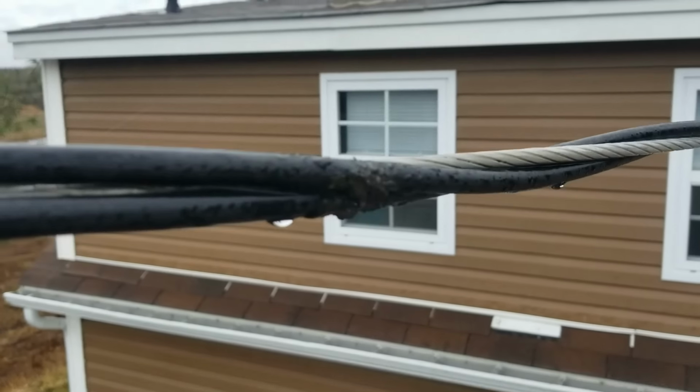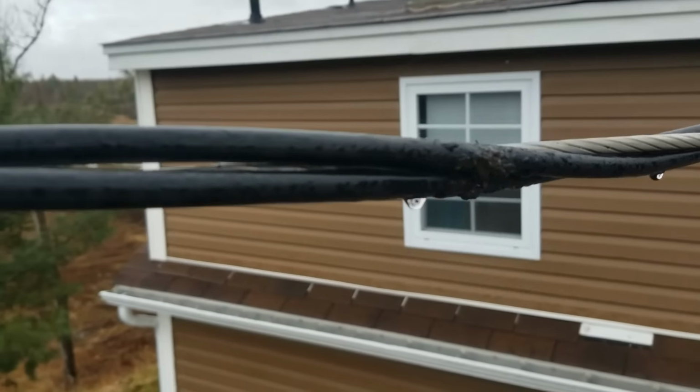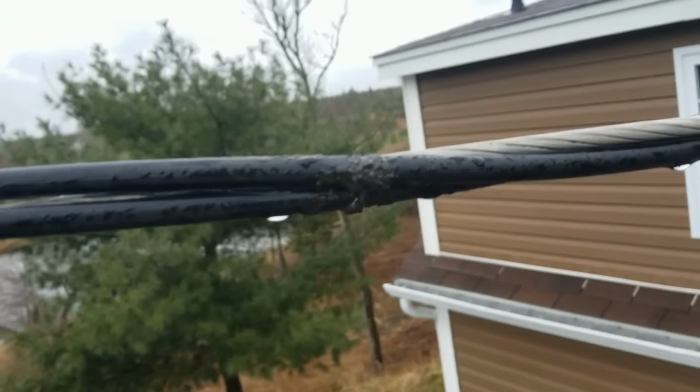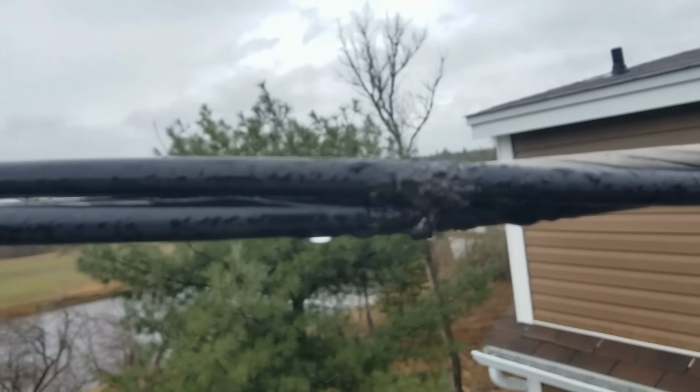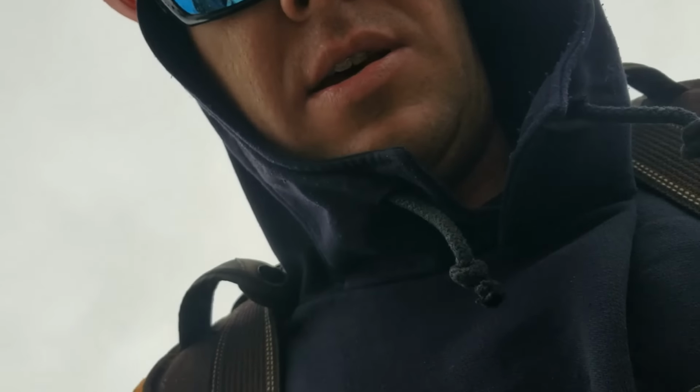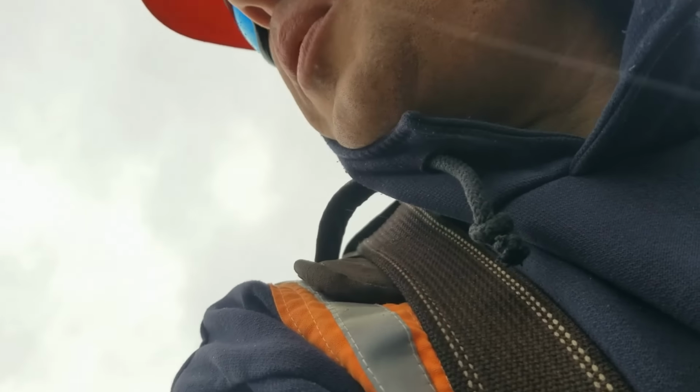Now it's not broken or nothing. It doesn't look like burn marks. Let's see what's going on, but if I didn't just check voltage there and find none and find 240 there, I'd never believe it, but it almost seems like we're losing our voltage right there in that wire. So before I go disturbing that, if I start moving it around, she might short out against that neutral, get a big ball of fire in my face. So I'm gonna go, I can either cut the blacks at the pole or open that transformer.